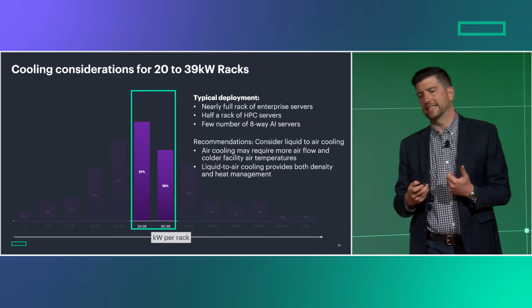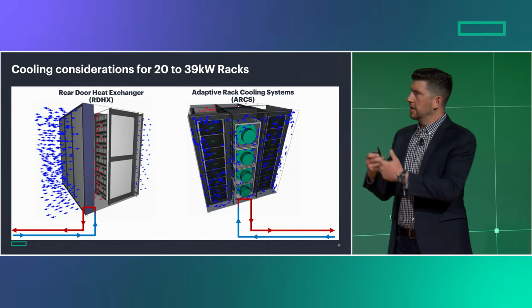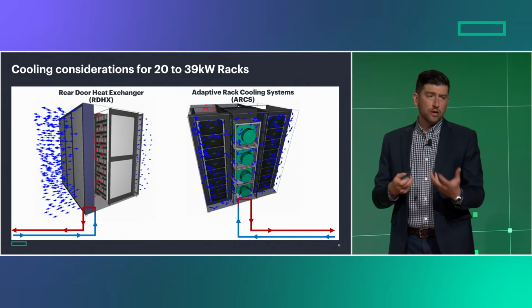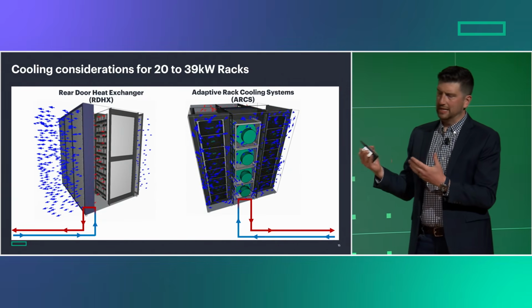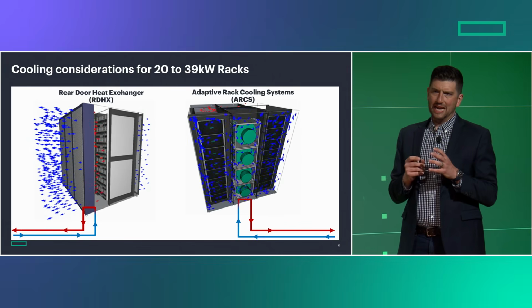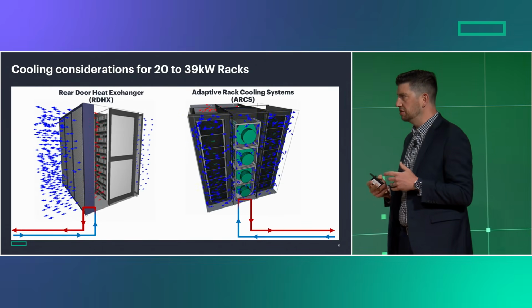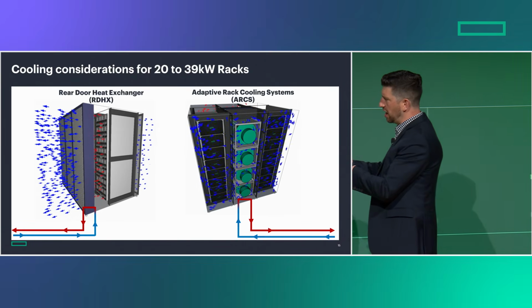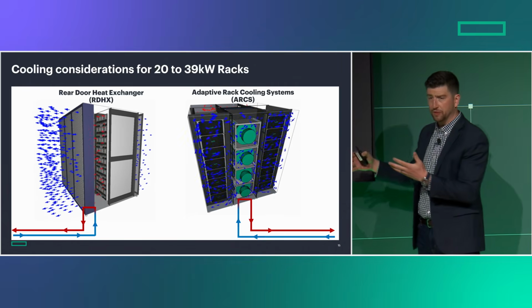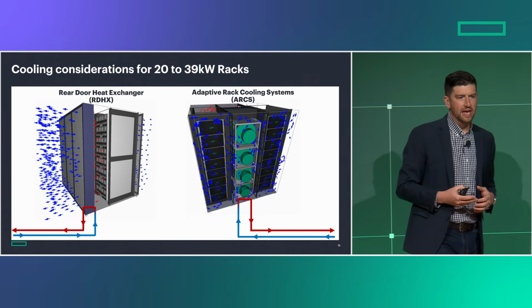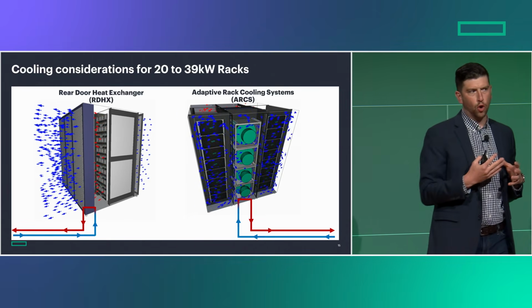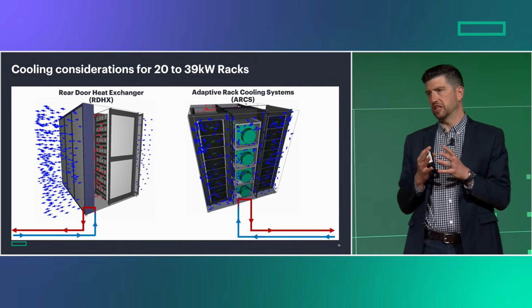For example, this would be something like a rear door heat exchanger, an in-row cooler, or our ARCS adaptive rack cooling system. The main principle behind this technology is we're going to take facility water, a cold water loop that's chilled from the data center, and pump it directly into a coil that sits very close to the IT.